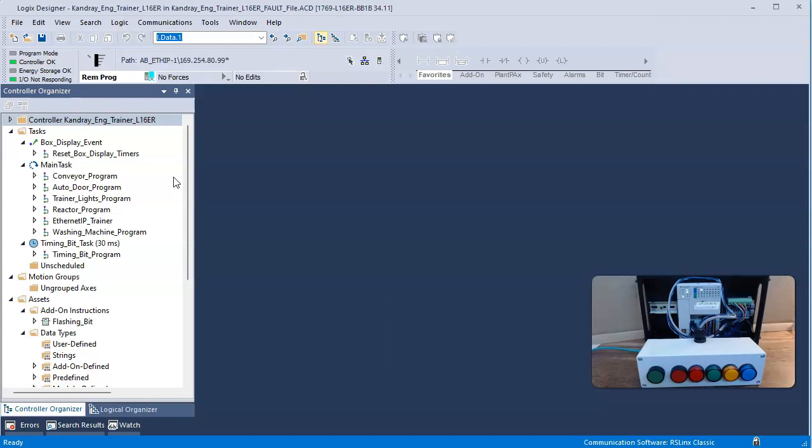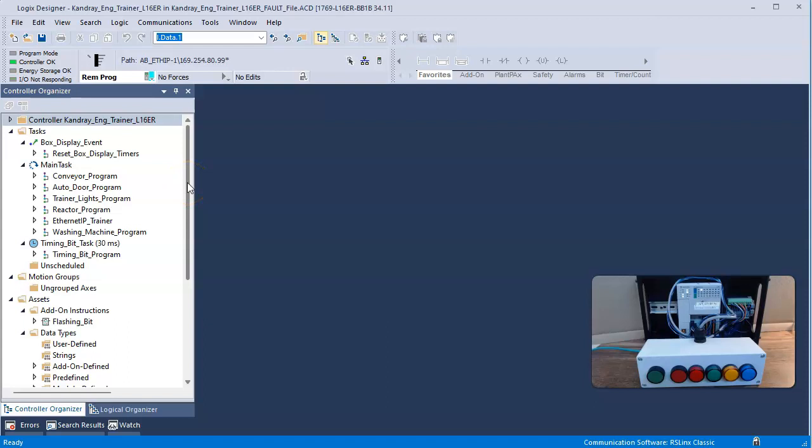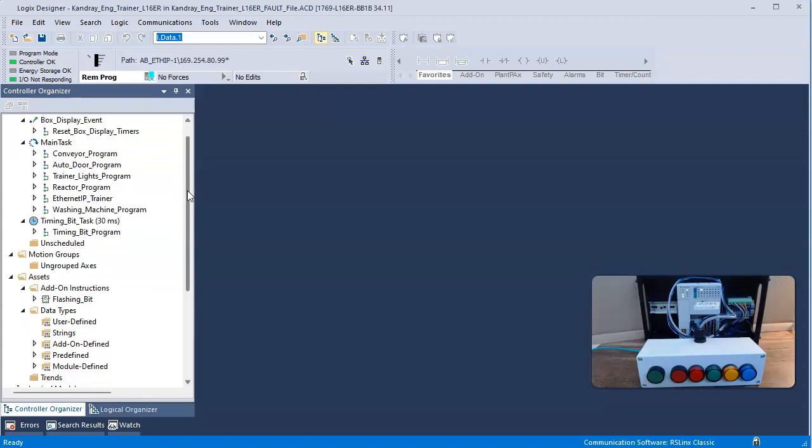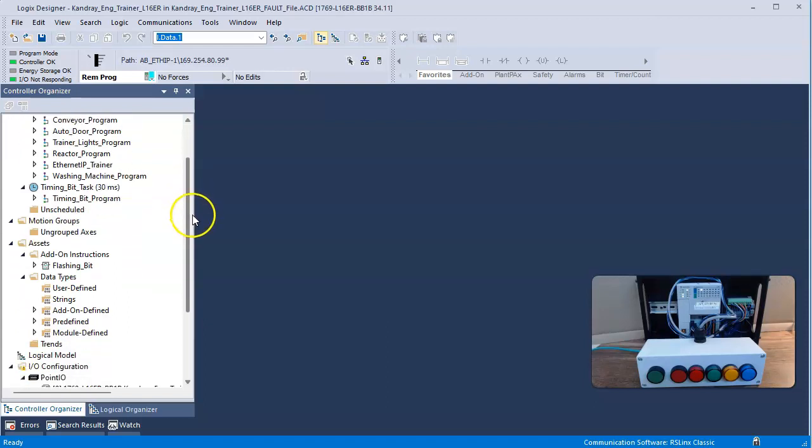As quickly as possible, perhaps the most prudent thing to do at this point is to re-download the master file for the machine. The program could be corrupt. We could still have a hardware issue, but the program could be corrupt. So for peace of mind, I'll typically re-download the master file and see if that remedies the situation. If it does not, or in lieu of that, I can investigate a little deeper.